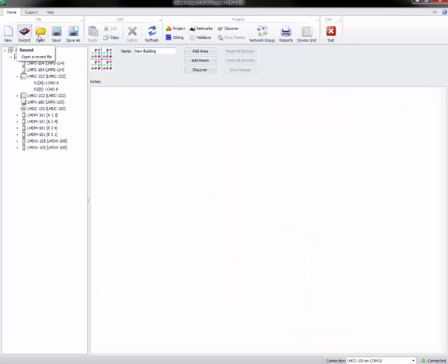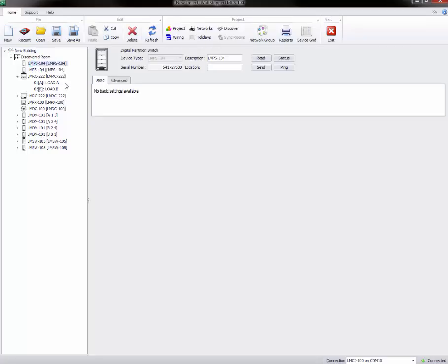So back to LMCS. What you can do, the LMPS-104 is an LMCS. There's not a whole lot you can do. You still have to physically push and enable the top button. In this case, you only have one partition, so we only want to enable one button. Push and hold it for 10 seconds. That will enable it. And then subsequent pushes to activate or deactivate the wall are only a 3-second push. So I don't need to worry about labeling these ones.